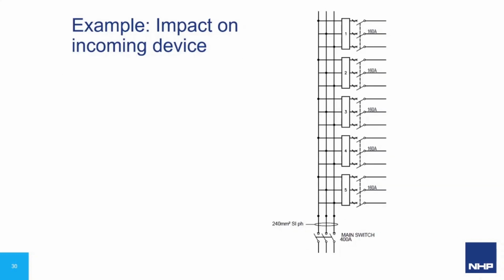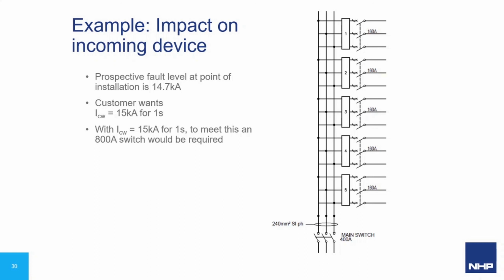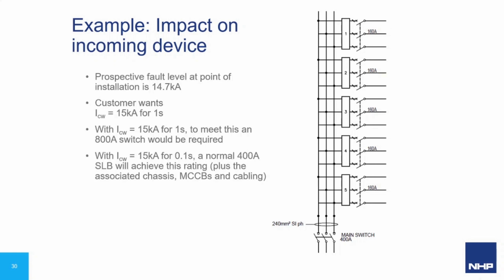In this example, we will look at how our three options could impact the selection of our incoming device. The prospective fault current nominated here is 14.7 kA. As is typical, this has been translated to a 15 kA for 1 second rating being requested by the end user. If we wish to satisfy the 15 kA for 1 second, we would need to upgrade the incoming isolator to 800 amps. We could consider downgrading the time rating to 15 kA for 0.1 seconds. This is quite reasonable, as most modern protection will clear the prospective fault in less than 1/3 of this time, in which case a normal 400 amp load break switch will achieve the rating of 15 kA for 0.1 seconds.